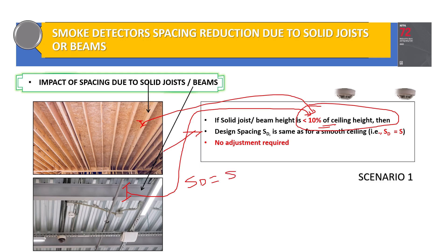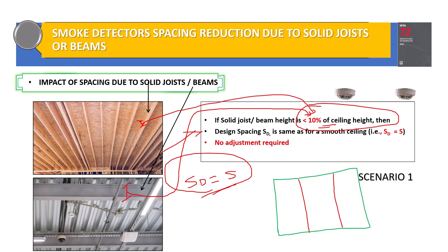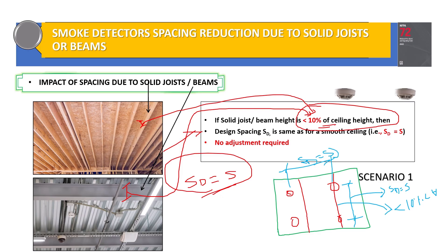In Scenario 1, the design spacing will be equal to the nominal spacing and no adjustment is required. So the design spacing SD equals S, both perpendicular and parallel to the beam or joist. S is the nominal spacing of 30 feet, so we use 30 feet by 30 feet. There is no reduction factor for this particular scenario.